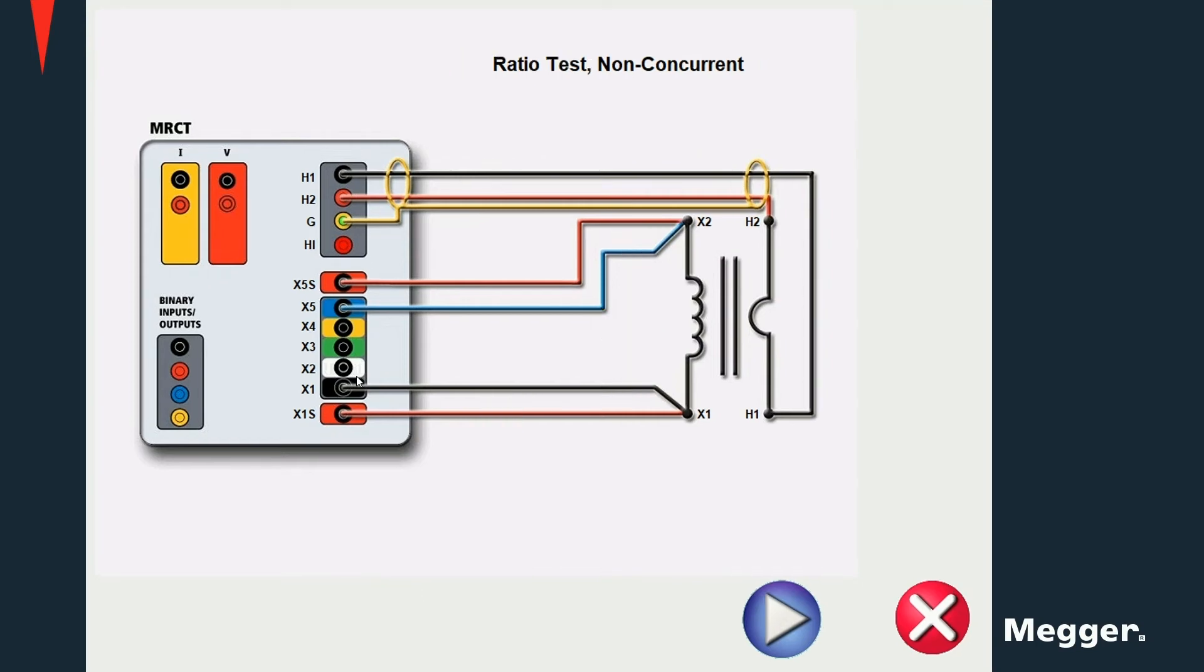For a ratio test, a voltage is injected into the secondary of the CT and measured on the primary side. And the ratio is calculated as the ratio between the voltage injected in the secondary and the voltage measured on the primary.